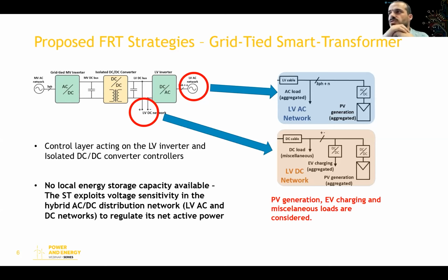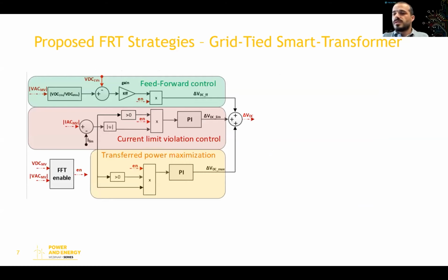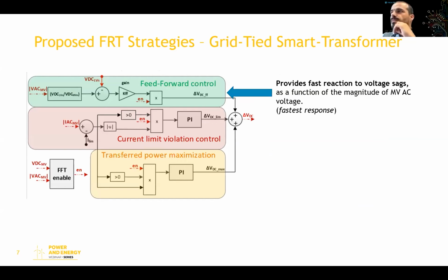Further, we implemented models for some distribution networks comprising PV generation, EV charging, and other loads, as represented here. The idea is that all of these devices are sensitive to the voltage. If you reduce the voltage on those grids enough, we can also reduce the power both consumed or generated. So the strategy consists of three elements. We have a feed-forward control, which provides a fast reaction to voltage sags as a function of the magnitude of the medium voltage AC in the DC network.